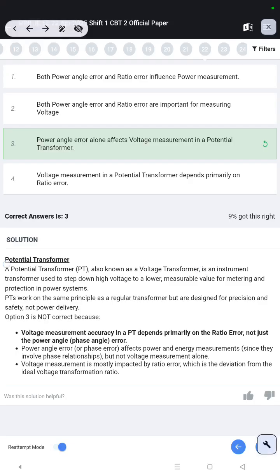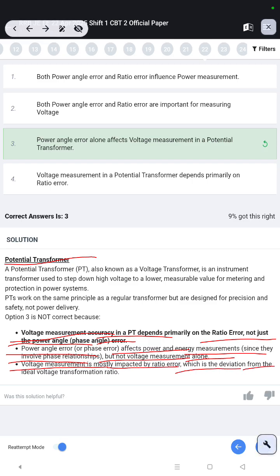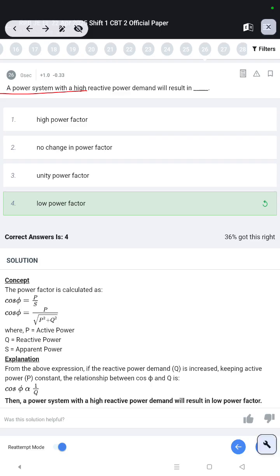In a potential transformer, voltage measurement accuracy depends primarily on the ratio error, not just the phase angle error. Phase angle error affects power and energy measurement involving phase, but not voltage measurement alone. Voltage measurement is mostly impacted by ratio error, which is the deviation from the ideal voltage transformation ratio. A power system with a high reactive power demand will result in low power factor.